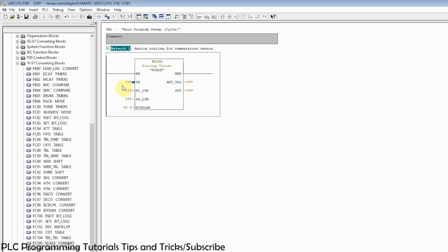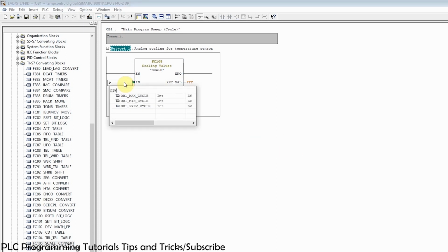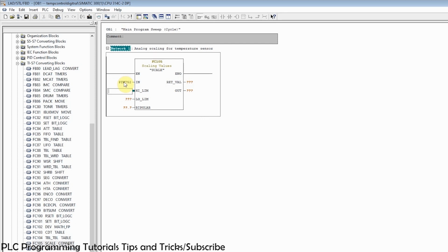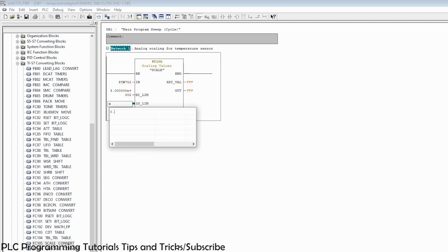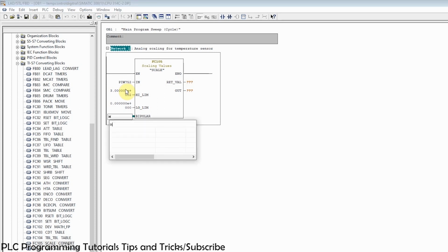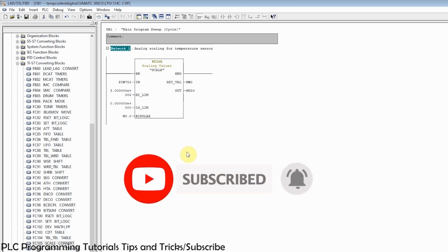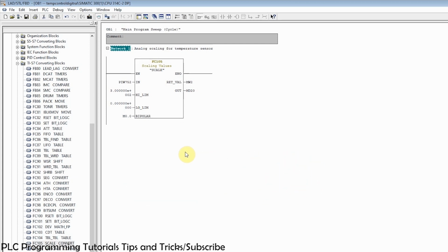First, we will enter the PIW752 word at the input of the scale function. The PIW752 word is to hold the analog values of the channel 0. Next, we will enter 300.0 at the high input and 0.0 at the low input of the scale function to scale the temperature transmitter signal to 0 to 300 degrees Celsius. Next, we will enter the MD20 at the out of the scale function. The scale function will store the scaled value of the temperature transmitter in the MD20 data register.